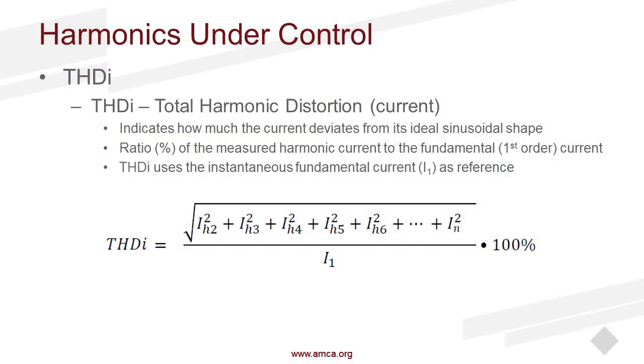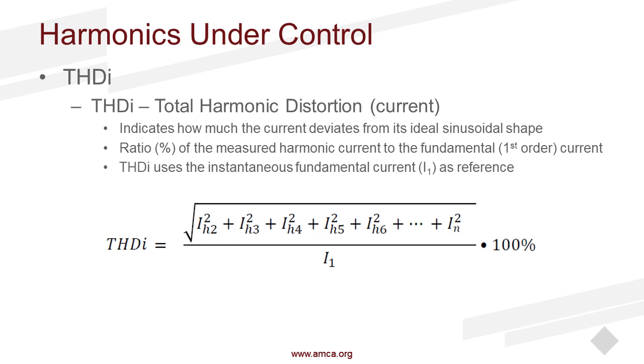So I wanted to explain a little bit more about TDD, THDI, THDV, what they are and what relationship they have, because I think there's a lot of confusion with it, especially with IEEE 519. So THDI is your total harmonic distortion. This is how much your current is deviating from that fundamental wave, which we were talking about in Fourier series. And so it's the measured harmonic current in ratio to your fundamental current. And here you can see the relationship where you have all your harmonic currents added together in ratio to your fundamental current.